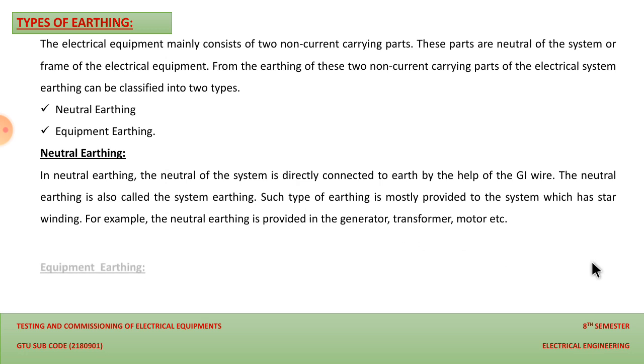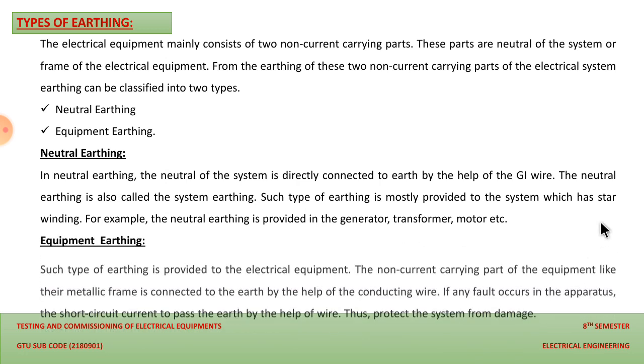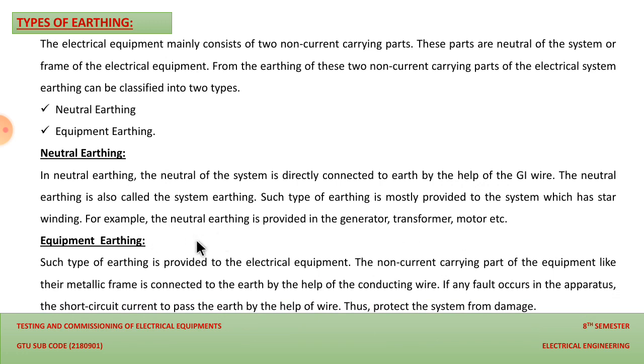Now let us discuss equipment earthing. What actually is equipment earthing? This type of earthing is provided to the electrical equipment. The generator and transformer are themselves electrical equipment, but the non-current carrying part of the equipment, like the metallic frame, is connected to the earth with the help of a conducting wire. So it is called equipment earthing, because in neutral earthing the neutral is connected with the GI or earth wire, and in this the body of the equipment is connected with the earth wire. That's why it is called equipment earthing.